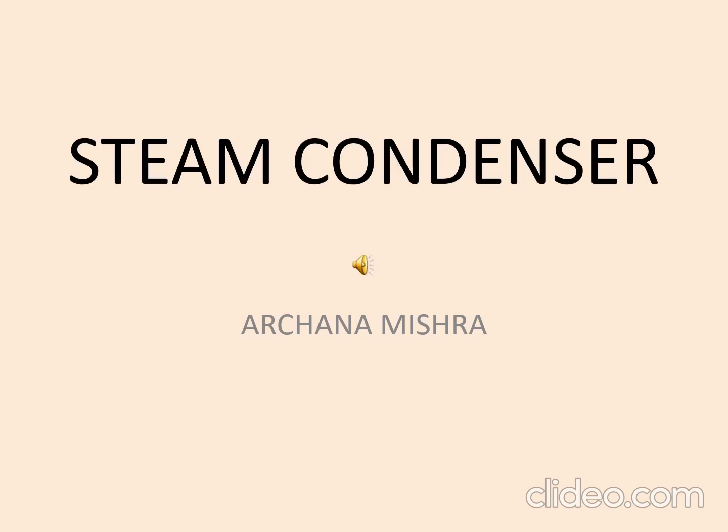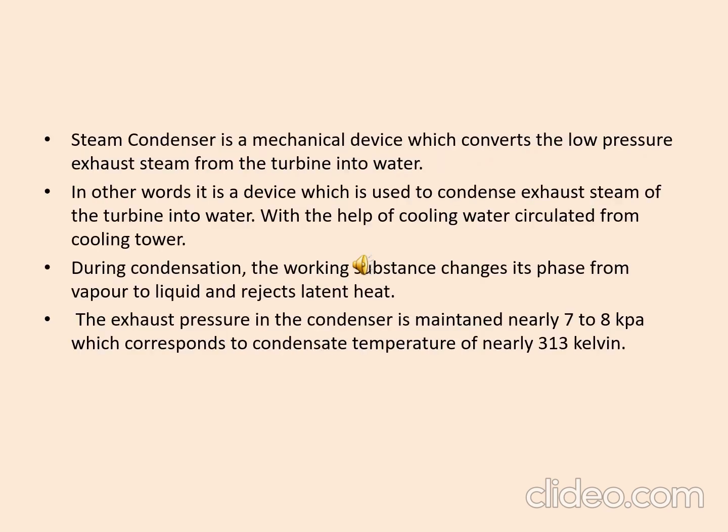We know that a steam condenser is a closed vessel which can maintain its pressure below atmospheric pressure, which will be 7 kilopascal or 8 kilopascal like this. It is also a heat exchanger which exchanges heat between the steam and the cold circulating water, so that its phase changes from steam or vapor to water.